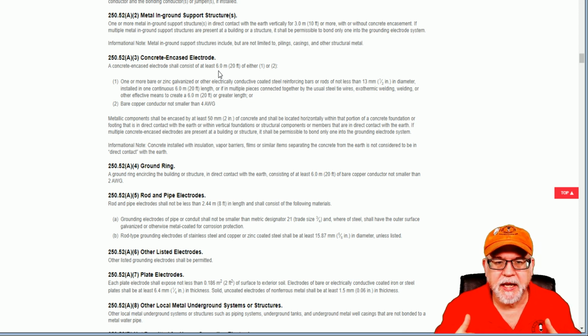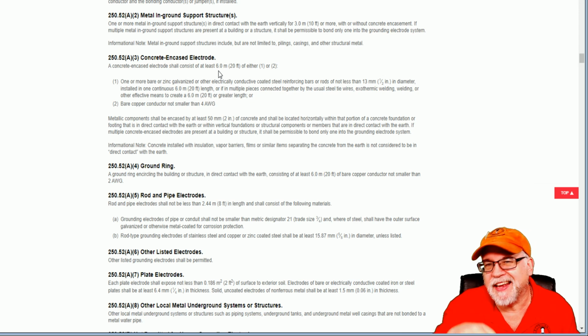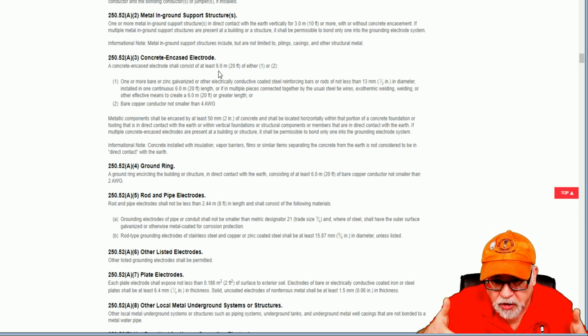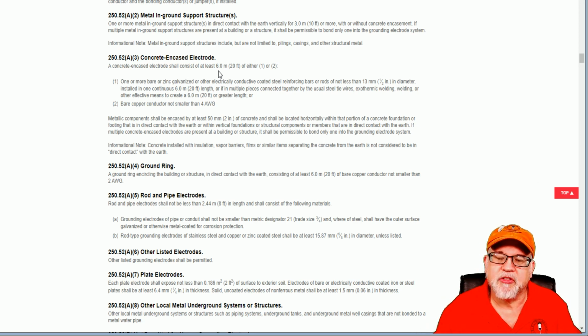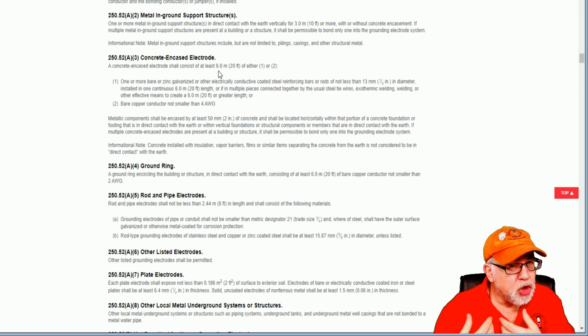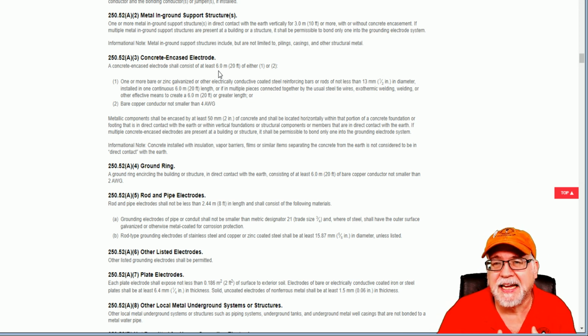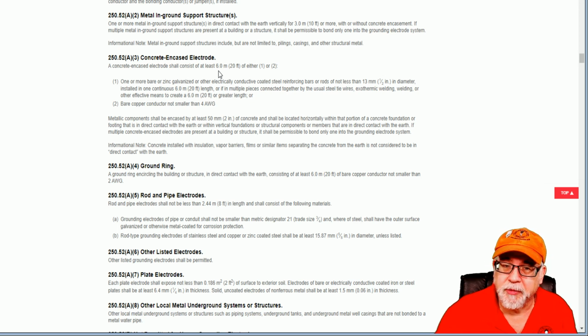And it's typically going, or we could actually have bare copper or 4 gauge that's in the actual concrete footer. And it's in contact with the earth through the concrete. Concrete's in contact with the earth. So that's inherent to construction. It's not something that me and you as an electrician are going to do, but we have to make that connection. So there's a timing thing. You got to make sure you're there in order to make that connection.